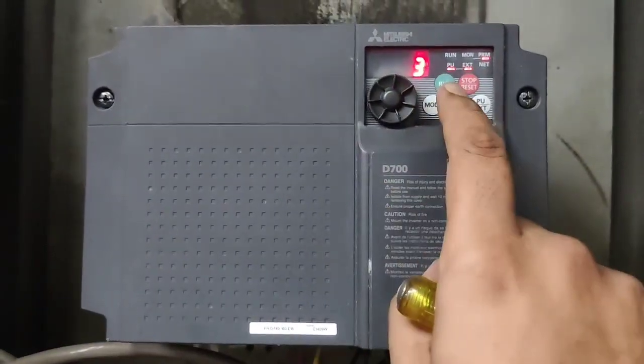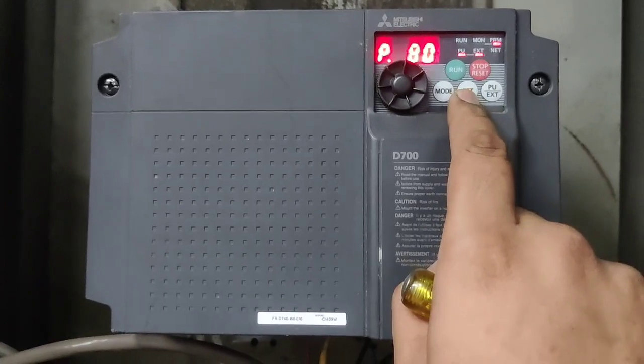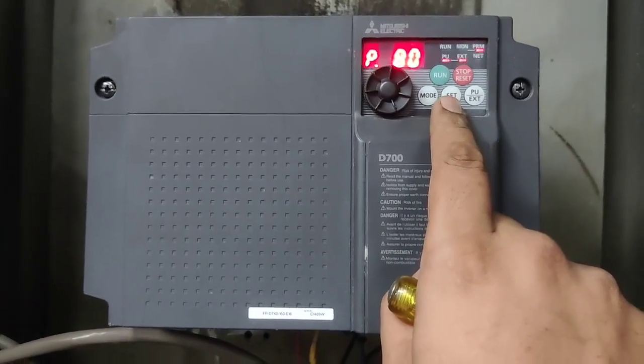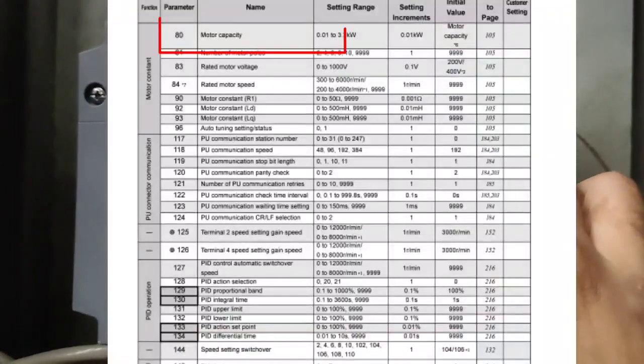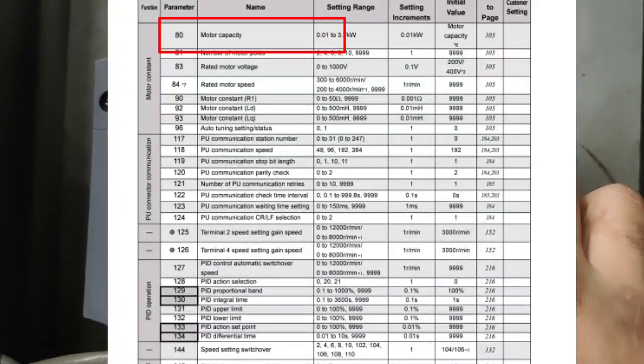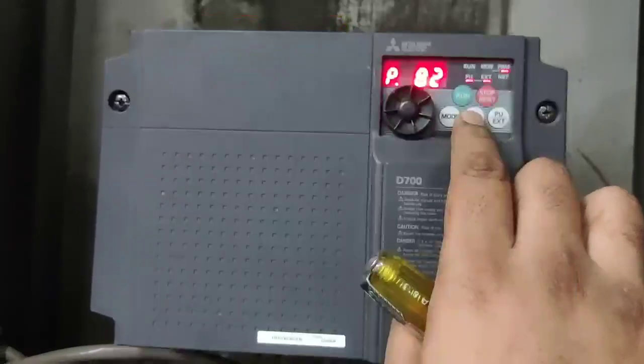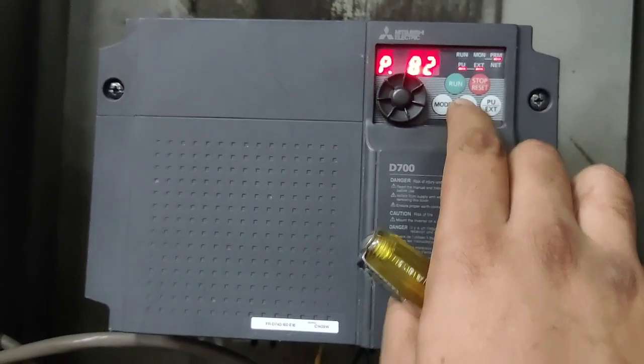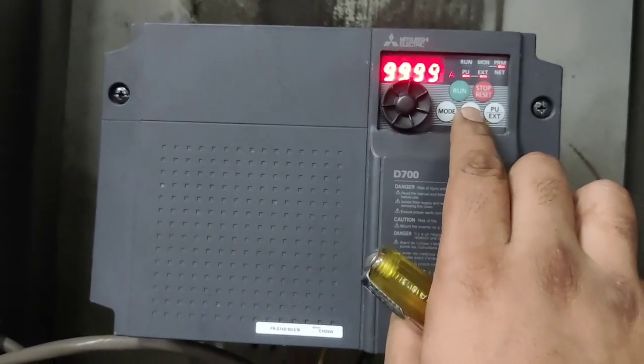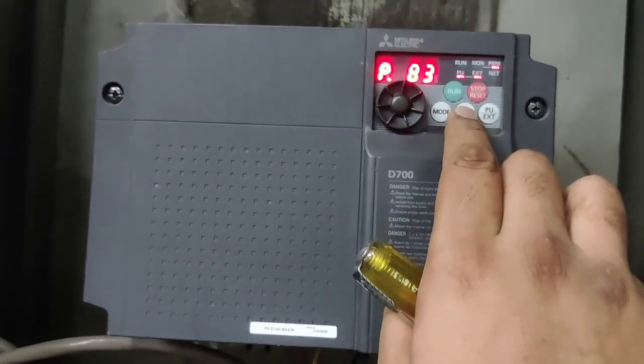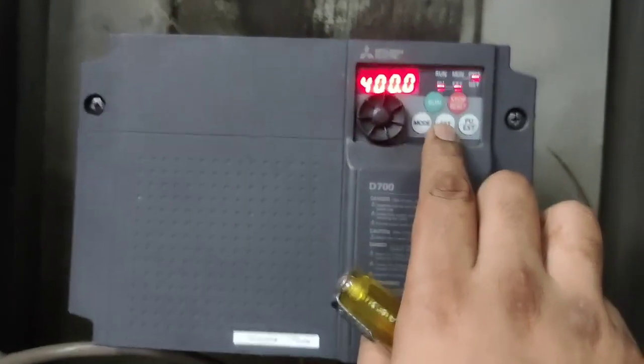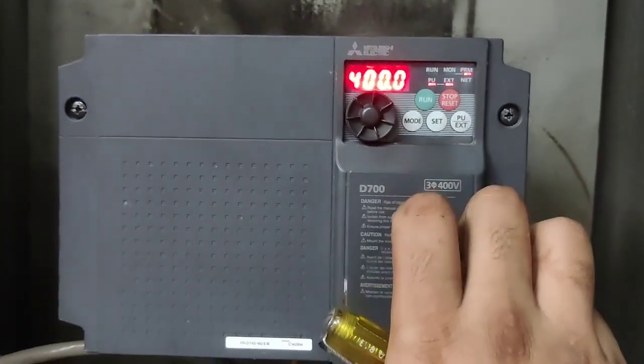Next parameter is P80, which is the motor capacity parameter — enter your motor kilowatt value here. P83 is for motor rated voltage — we set 400 V for motor rated voltage in P83.